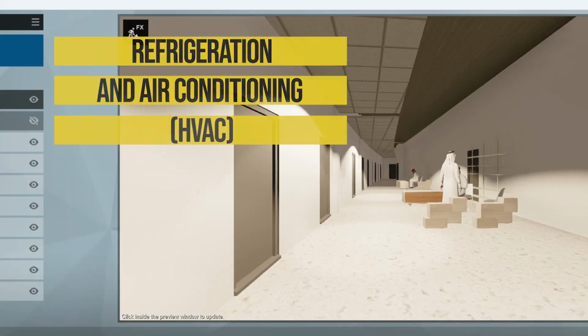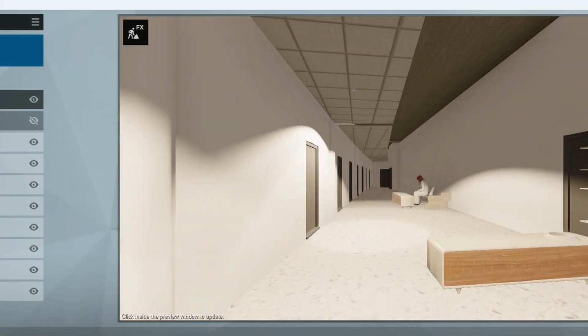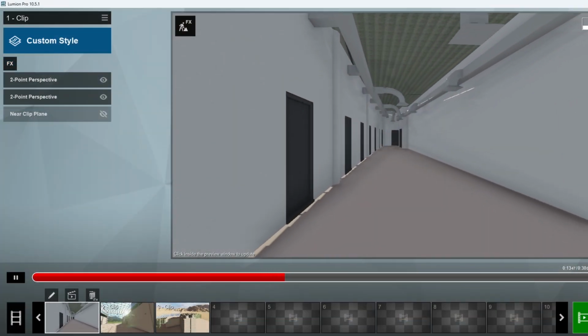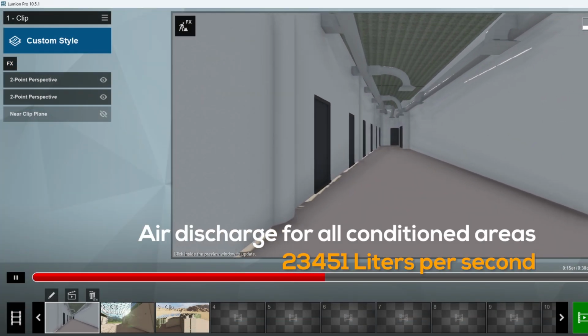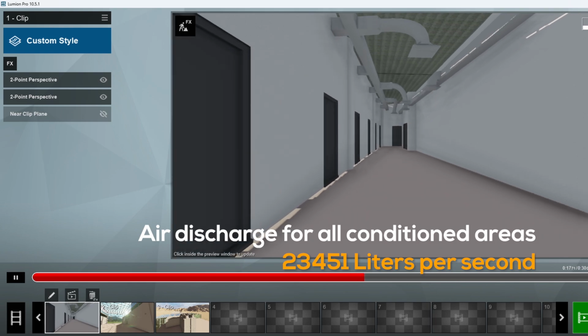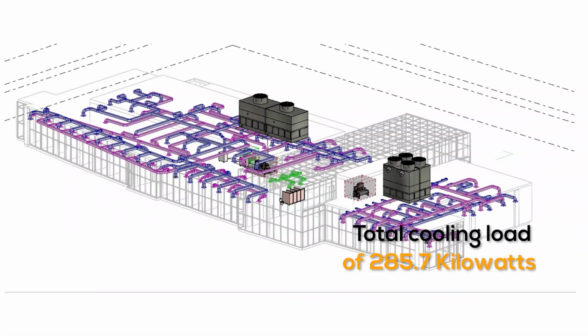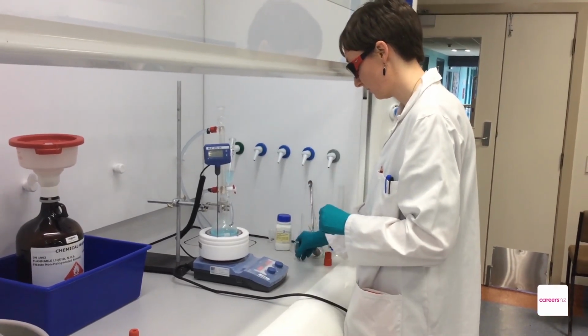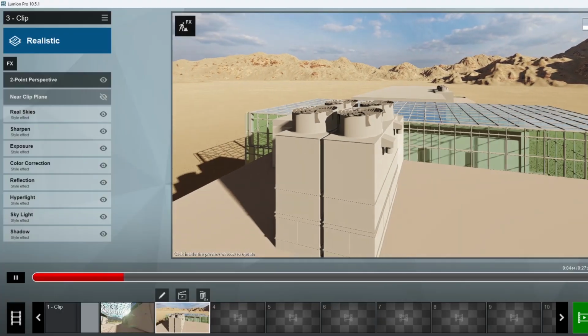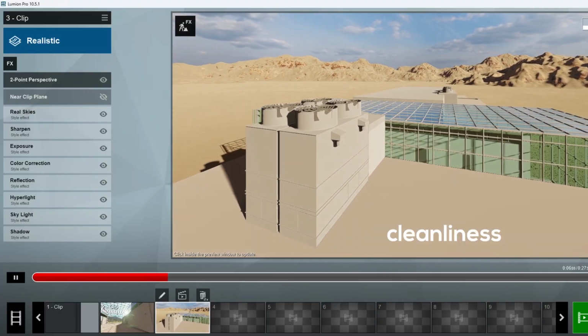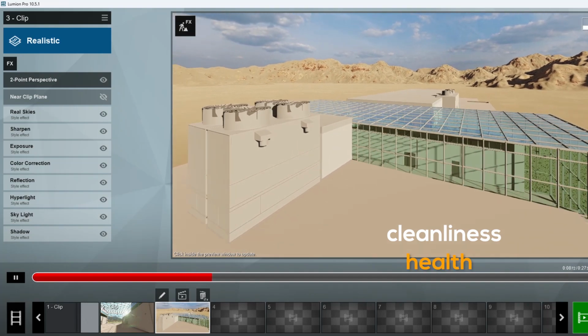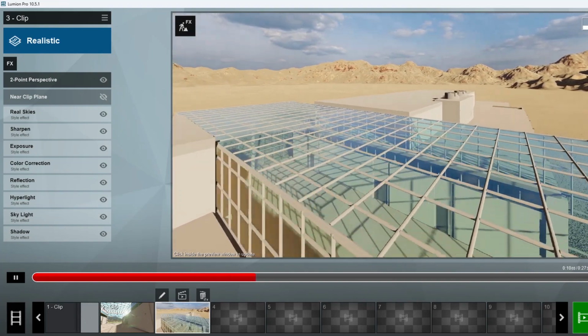Refrigeration and air conditioning. The application of the air conditioning system, based on the results of the cooling load calculation, obtained an air discharge for all conditioned areas of 23,451 liters per second and a total cooling load of 285.7 kilowatts. Chemical laboratories need an air conditioning system specifically designed to maintain the cleanliness and health of the air in the chemical laboratory room, as well as provide comfort for its users.